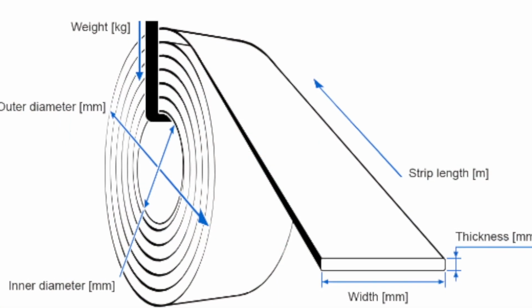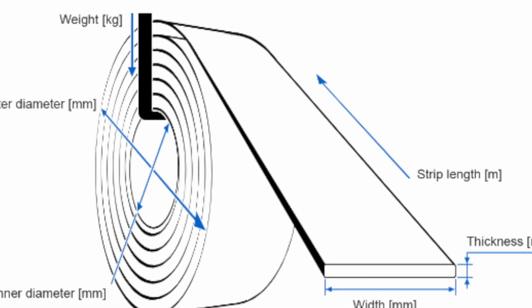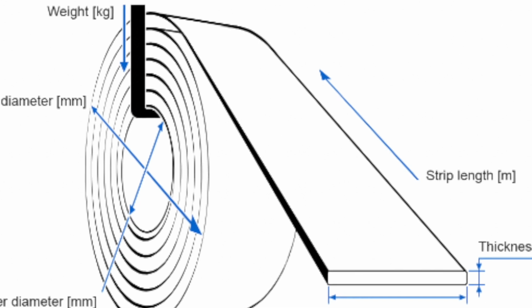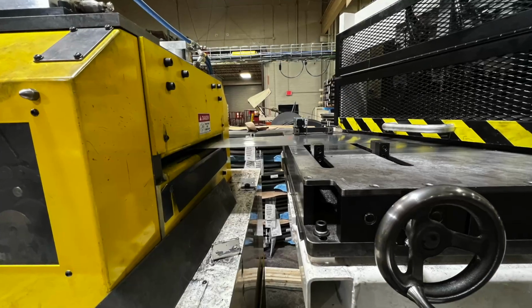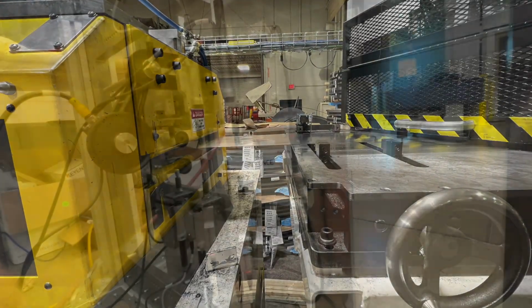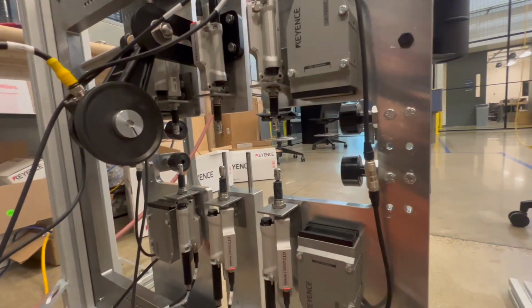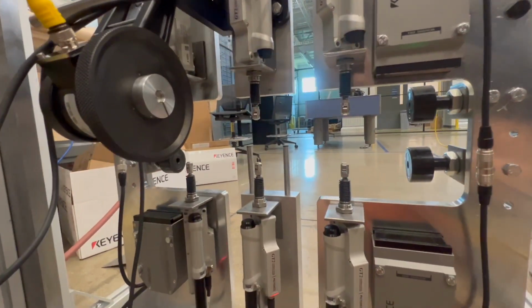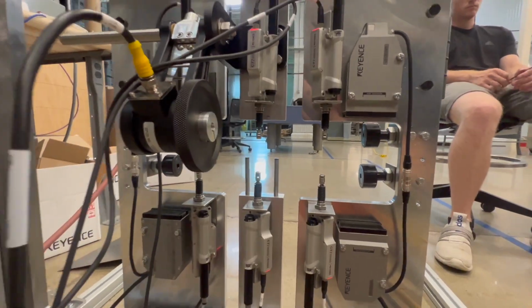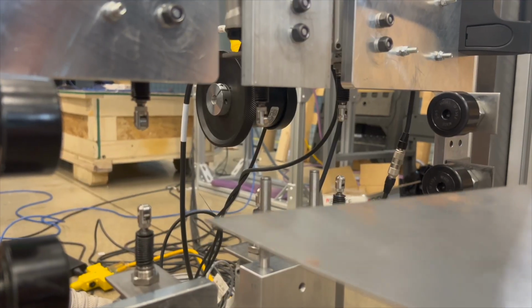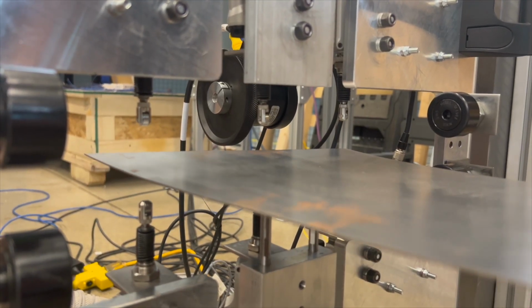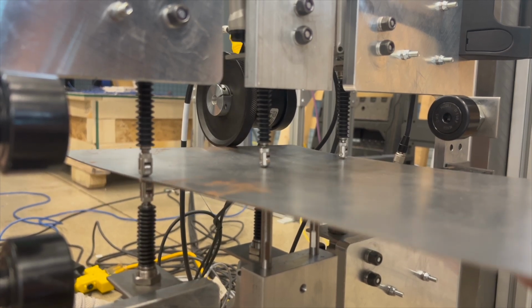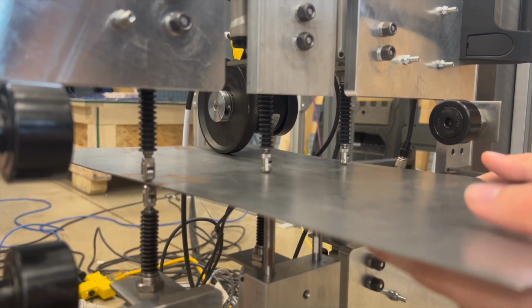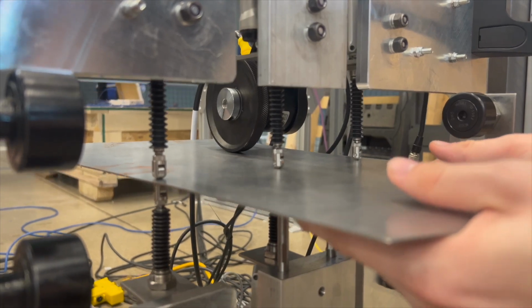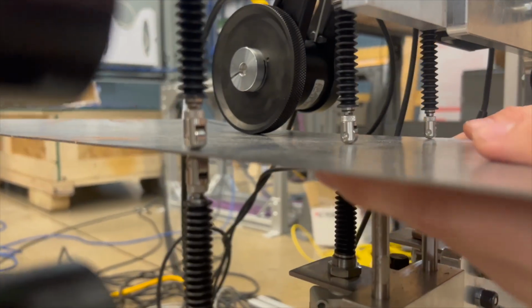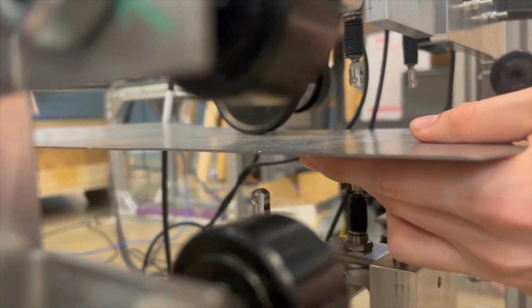For the key specifications, we will be measuring the thickness, width, and the crown or the bending of the sheet. The standard for reading measurements is to have an accuracy of 10 times the tolerance. This leaves us with an accuracy for the width, thickness, and crown of 0.025 millimeters, 0.016 millimeters, and 0.016 millimeters respectively.